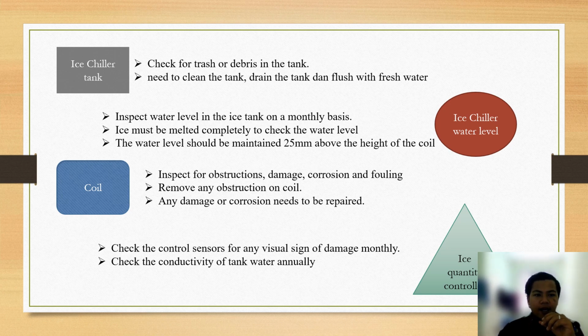There are several processes that need to be done at each component. The first one is the ice chiller tank. It needs to be checked for trash or debris in the tank. After that, clear the tank, drain the tank and flush with fresh water. For the ice chiller water level, inspect the water level in the ice tank on a monthly basis. After that, the ice must be melted completely to check the water level. And lastly, the water level should be maintained 25 mm above the height of the coil.